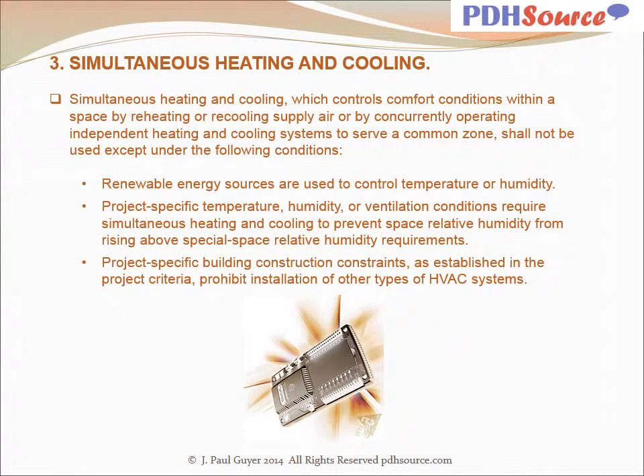Simultaneous heating and cooling, which controls comfort conditions within a space by reheating or recooling supply air or by concurrently operating independent heating and cooling systems to serve a common zone, shall not be used except under the following conditions. Renewable energy sources are used to control temperature or humidity. Project-specific temperature, humidity, or ventilation conditions require simultaneous heating and cooling to prevent space relative humidity from rising above special space relative humidity requirements. Project-specific building construction constraints as established in the project criteria prohibit installation of other types of HVAC systems.